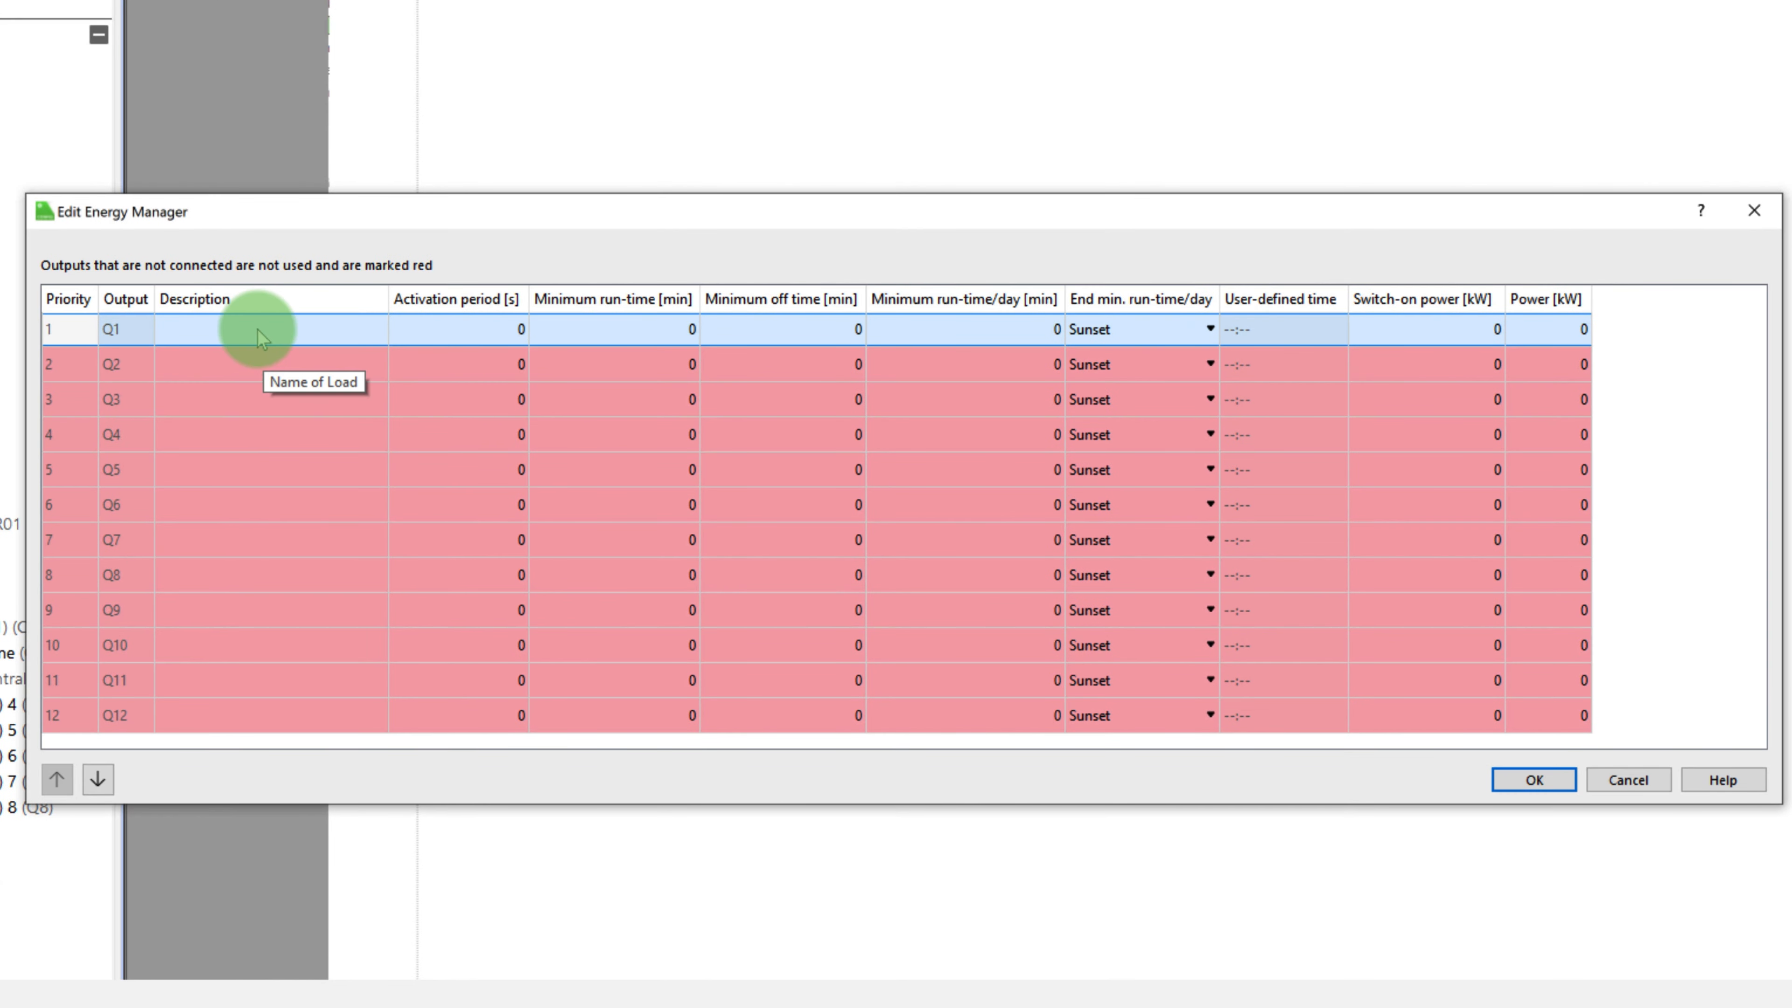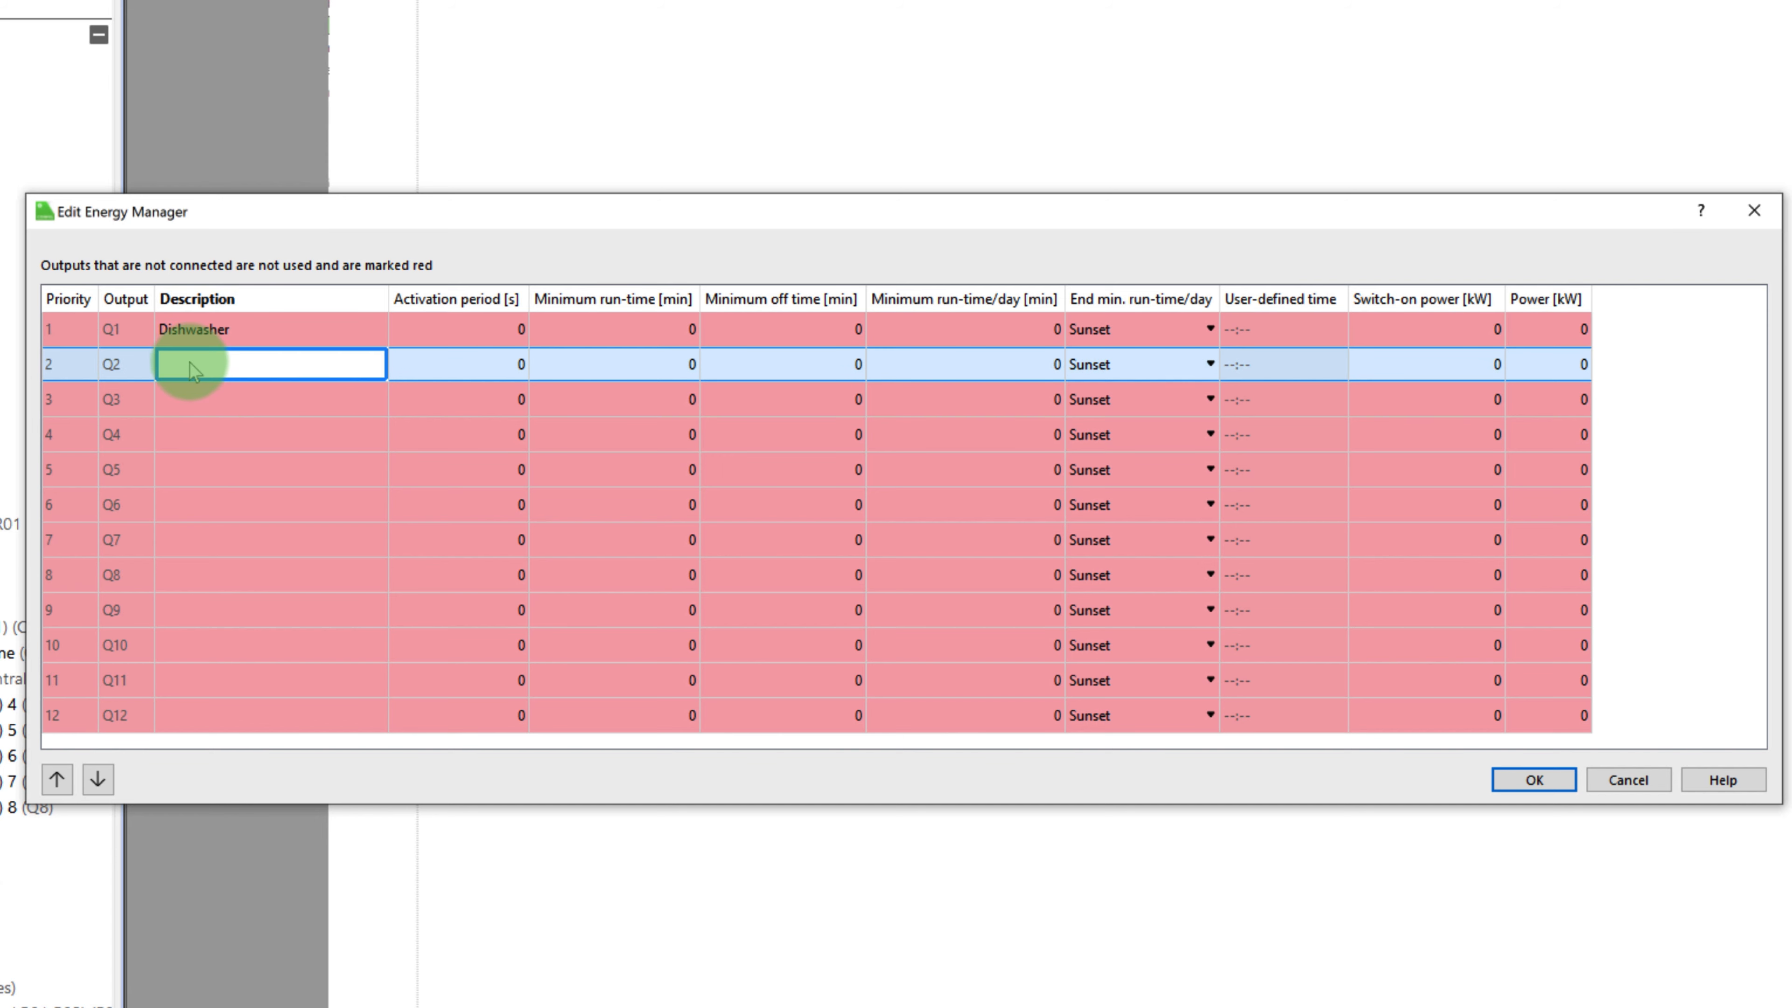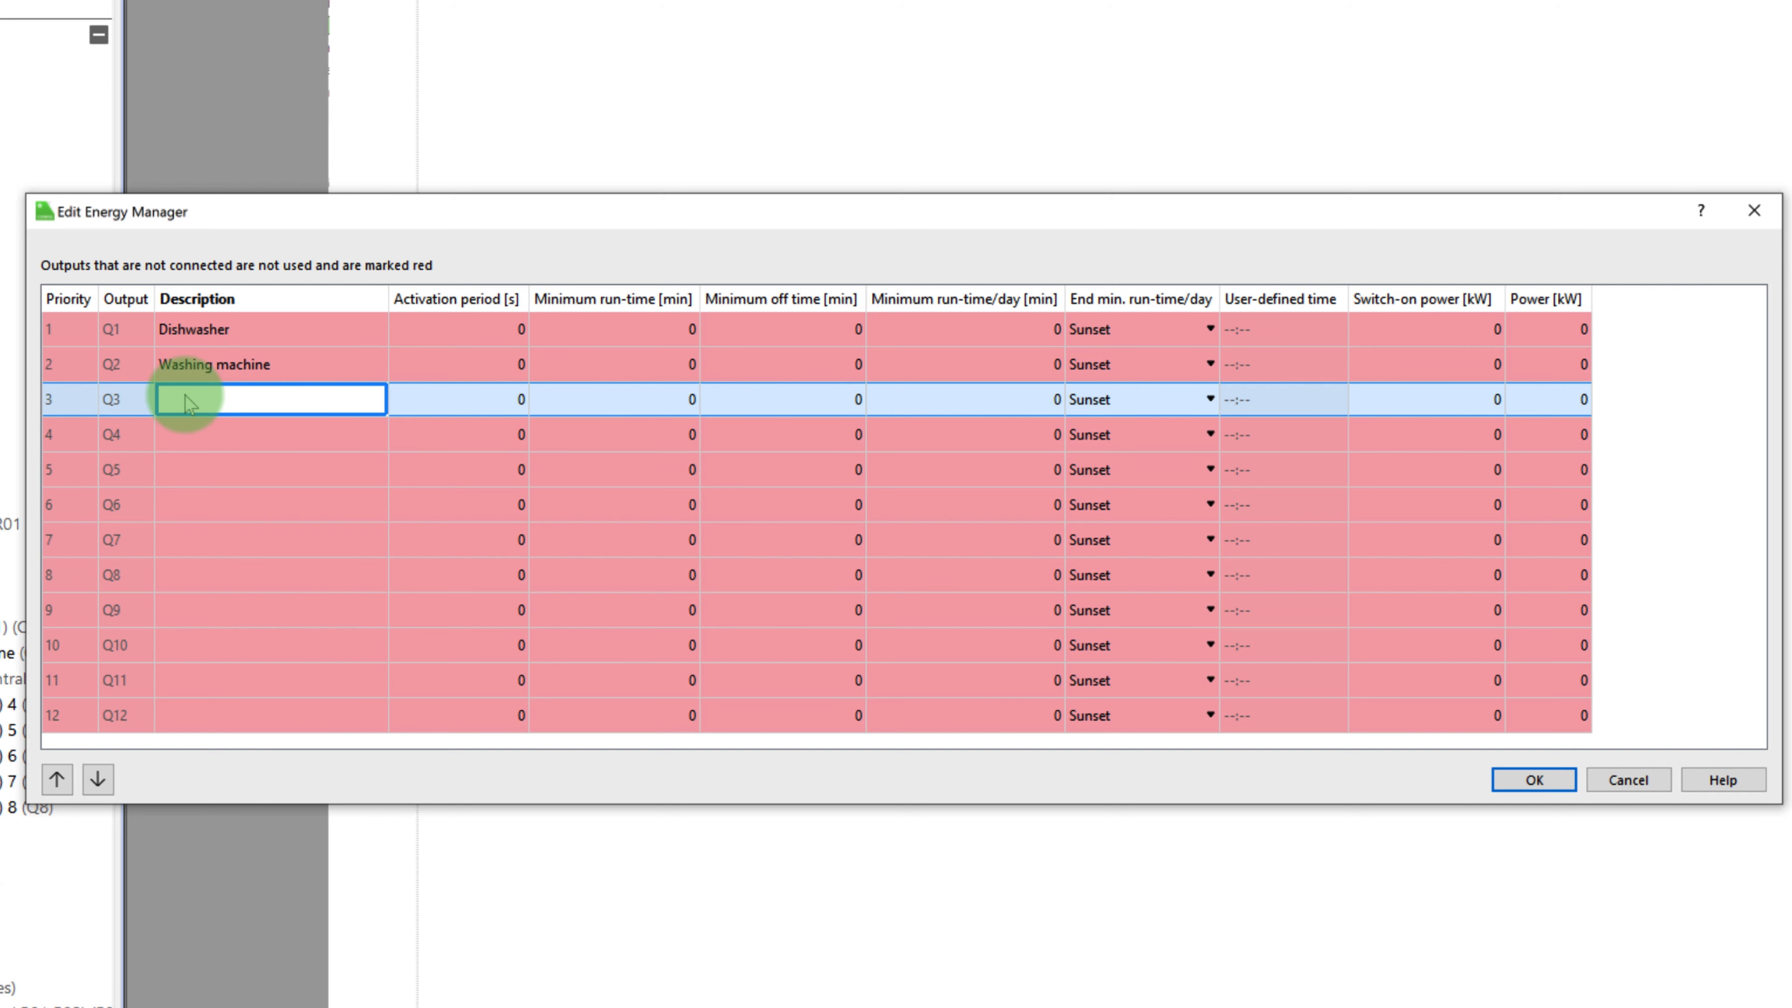These devices are assigned priorities, with 1 being the highest priority and 12 being the lowest. If there is excess power at input AIP, the Energy Manager switches on as many devices as possible, starting with the highest priority.